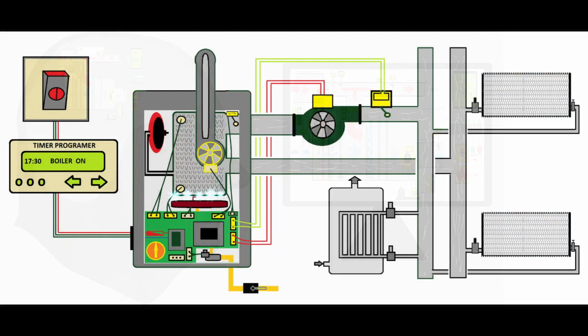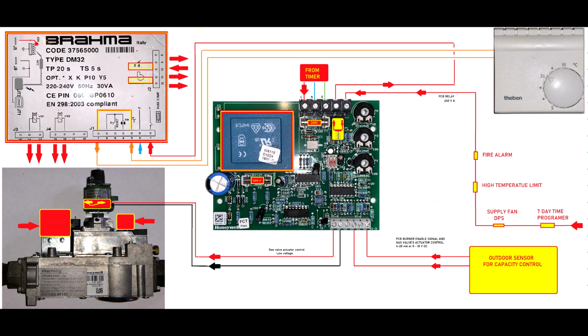Guys, I did many other videos which explain how boilers work, what the control philosophy is, and what the sequence to run a boiler is. The main thing is that before you repair something, I think you first have to understand how that something works. Now let's say that in these circumstances you don't want to waste your money on an expensive building management control or on a programmable logic control. You only want to use a thermostat and probably a probe that has the capability to supply 0 to 10 volts or 4 to 20 milliamps directly to this printed circuit board.